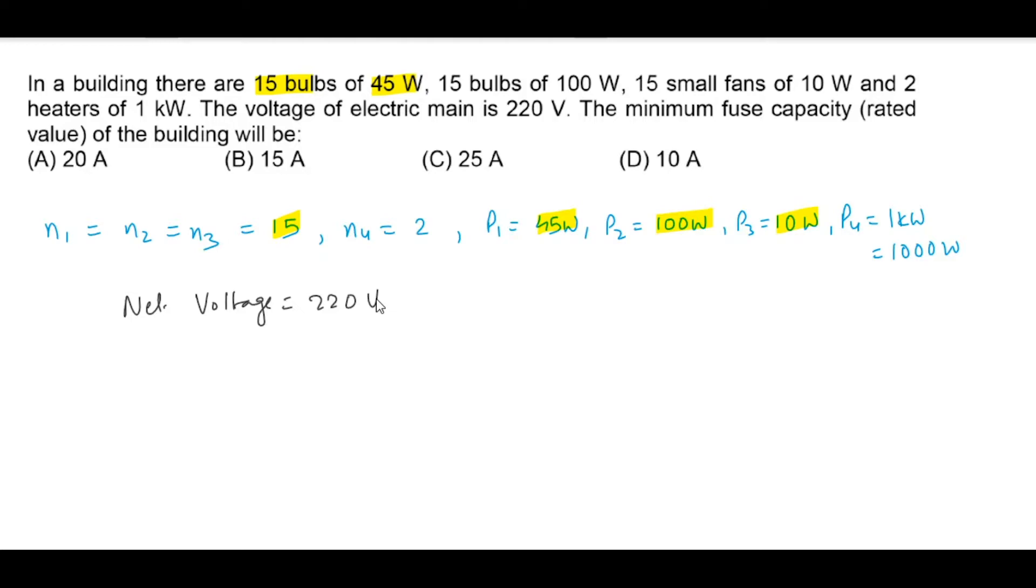So here the total power consumed, that would be P equals 15 into 45 plus 15 into 100 plus 15 into 10 plus 2 into 1000. This equals 4325 Watts, so this is the total power required in Watts for the whole building.